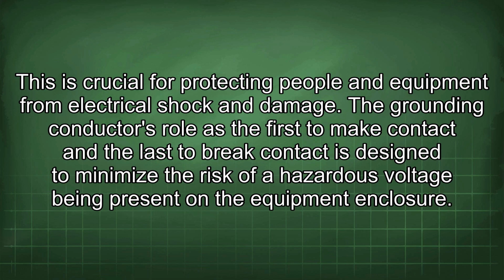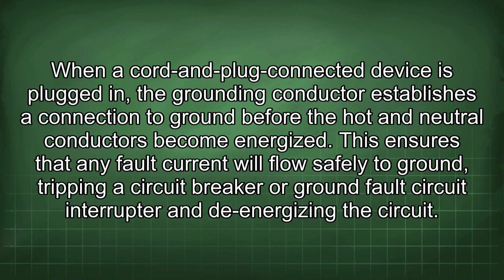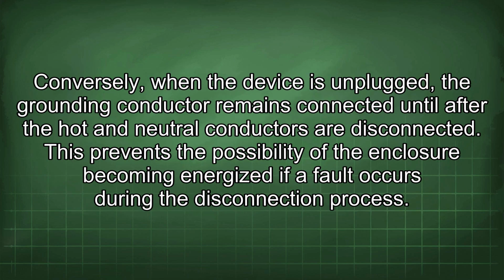The grounding conductor's role as the first to make contact and the last to break contact is designed to minimize the risk of a hazardous voltage being present in the equipment enclosure. When a cord and plug connected device is plugged in, the grounding conductor establishes a connection to ground before the hot and neutral conductors become energized. This ensures that any fault current will flow safely to ground, tripping a circuit breaker or ground fault circuit interrupter and de-energizing the circuit. Conversely, when the device is unplugged, the grounding conductor remains connected until after the hot and neutral conductors are disconnected. This prevents the possibility of the enclosure becoming energized if a fault occurs during the disconnection process.